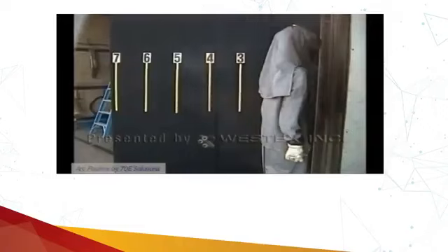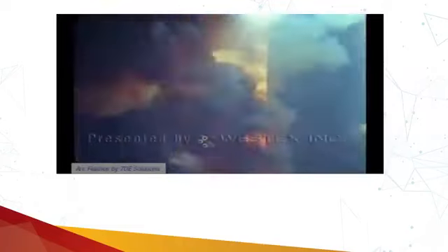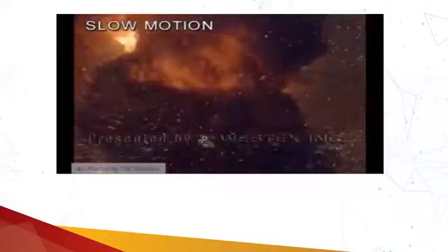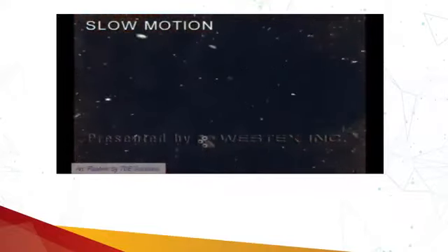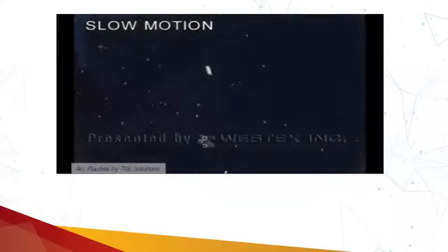No fire on the 40 cal flash suit. Slow motion, this is a massive arc. You can see the cycles pulsing and pulsing and pulsing, and molten metal going everywhere. Huge arc. And yet, because it was a 40 cal flash suit designed to handle an arc of this intensity, there is no fire.